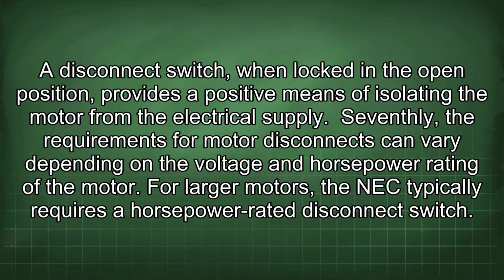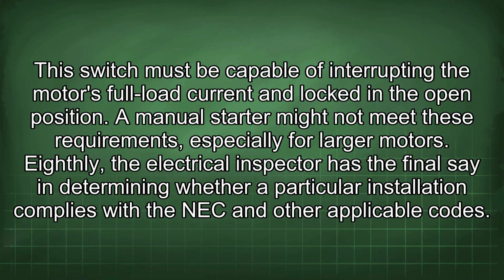Seventhly, the requirements for motor disconnects can vary depending on the voltage and horsepower rating of the motor. For larger motors, the NEC typically requires a horsepower-rated disconnect switch. This switch must be capable of interrupting the motor's full load current and locked in the open position. A manual starter might not meet these requirements, especially for larger motors.